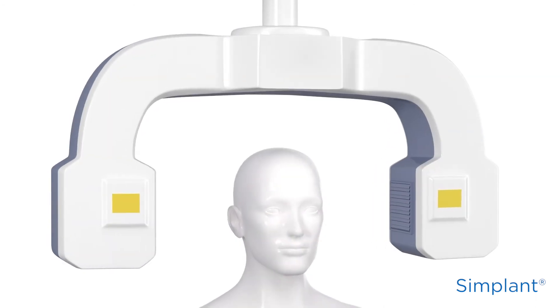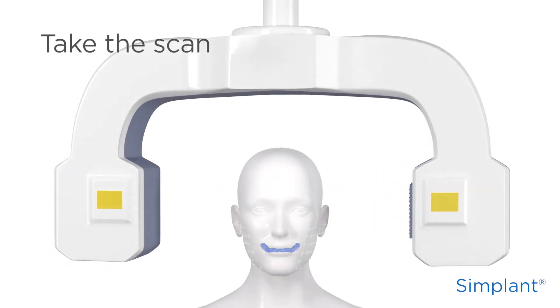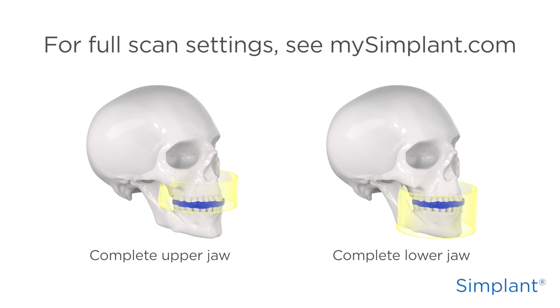Now that you've made the bite index, you can take the scan. Don't forget to scan the patient with the bite index. The complete upper or lower jaw, including the bite index, should be in the field of view. If you need more information on the scan settings, there's a small overview in mysimplant.com that you can use or send to your radiologist.